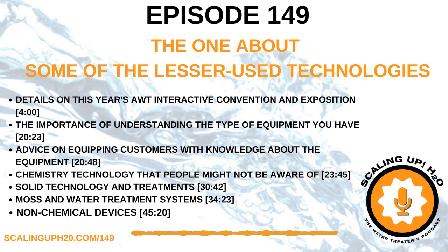This is the easy one to explain: if I'm maintaining X temperature of water and my stack temperature is 340 degrees, I know I'm wasting 340 degrees of heat. However, if I put this product in the water, reducing the surface tension, and now maintain the same temperature but my exhaust gas is only 310 degrees, I'm saving that heat and getting it into the water—heat you've already paid for that I'm going to add back.